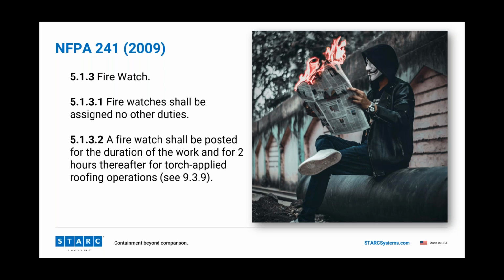I'll give you an example here. In that same section, it talks about when you're doing torched roof applications, you have to do fire watch for 2 hours after. I know personally, firsthand, of a hospital that had a fire occur right after they were applying a new roof, about an hour after application of the new roof, the fire started. The fire department ended up making the hospital evacuate the building. That's a whole other conversation for another day. But the fact is that this stuff does happen. There's a reason that this is in the code. There's a reason that we have to follow it. It's not if it's going to happen. You have to treat it as when it's going to happen.